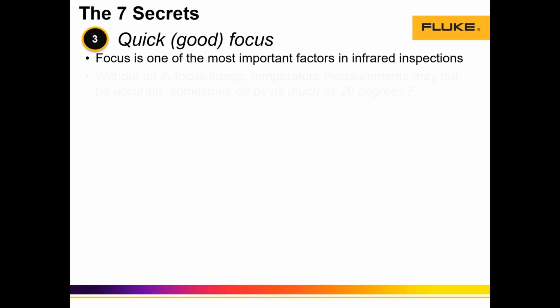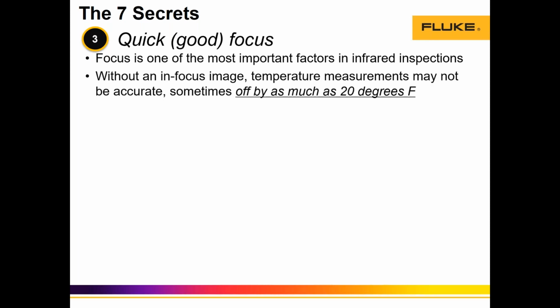So that takes us to the point of what tools we have to focus an image. We have manual and automated focus, but the key here is to understand that focus is so critical from an optical standpoint and from a measurement standpoint that without an in-focus image, our quantitative measurement can be as far as 20 degrees off, right? And also the image will look blurry and hard to understand or identify what assets we're inspecting, despite knowing that from the end user. So we have 2 problems, right? Number 1 is the quality of the focus, and number 2, how to do focus.